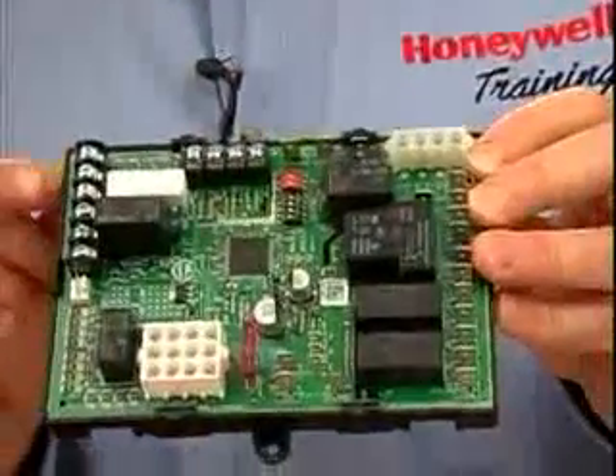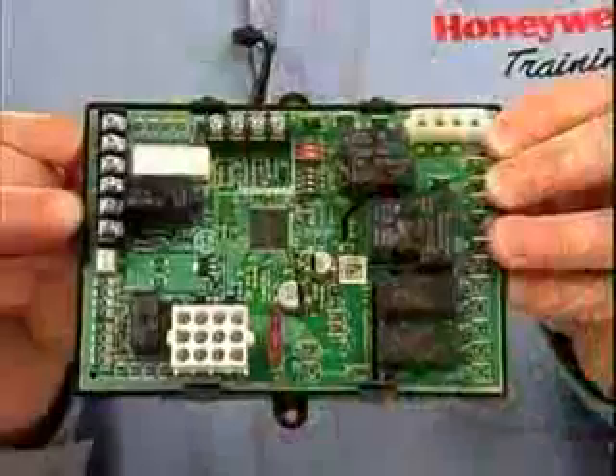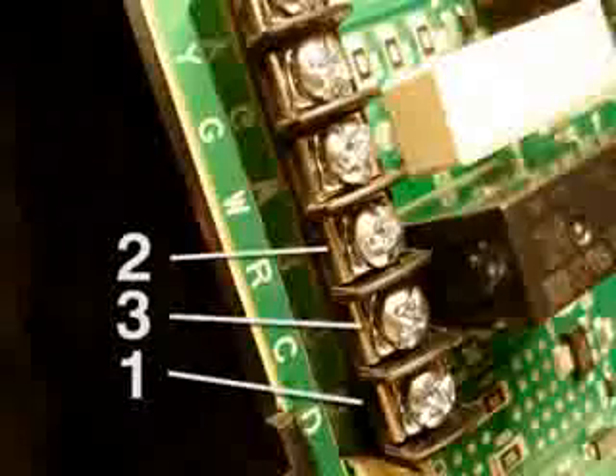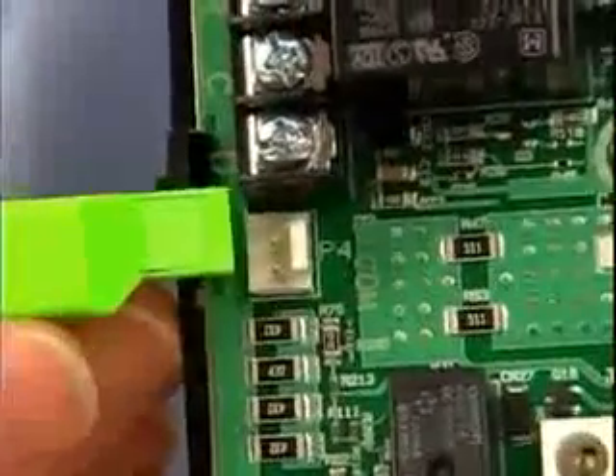Here are the familiar thermostat connections: Y, G, W, R, and C. It can also be controlled by an EnviraCOM thermostat, and those terminals are right here, 2, 3, and 1. And this connector is also for EnviraCOM, where you can plug in the OnWatch Quick Look 72 or some other diagnostic tool to read out flame signal and a possible fault condition.